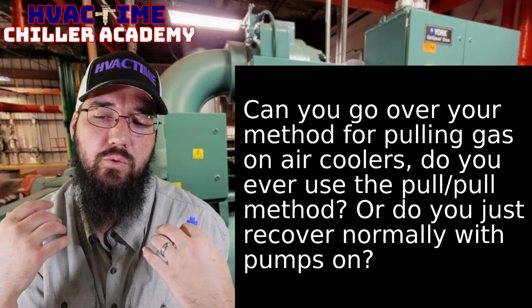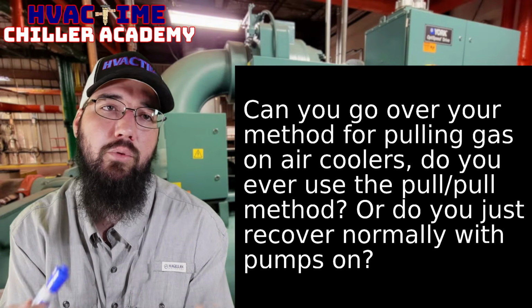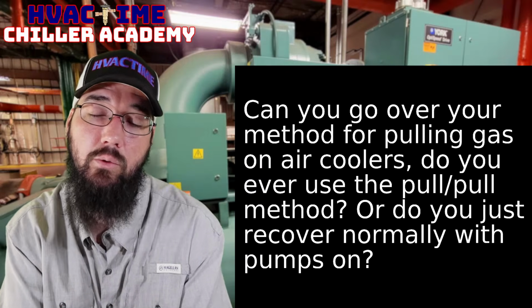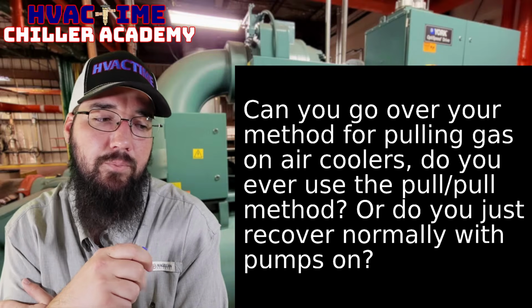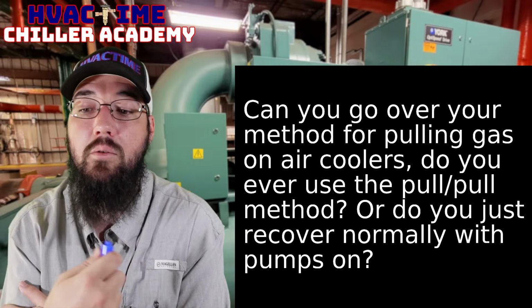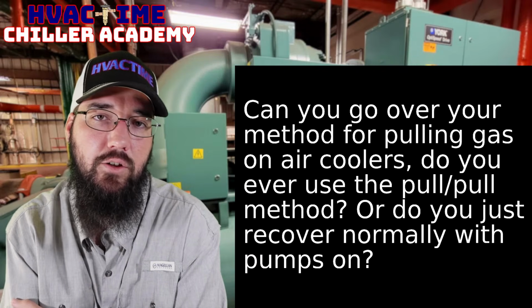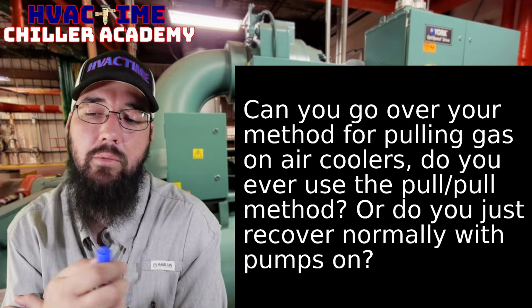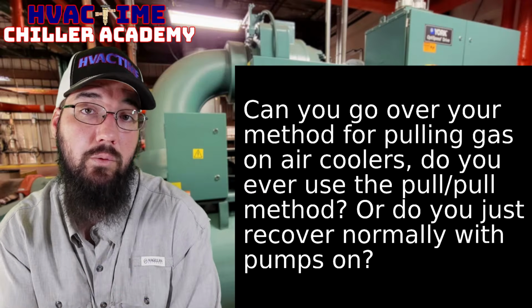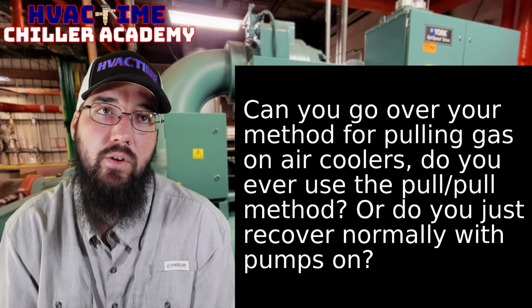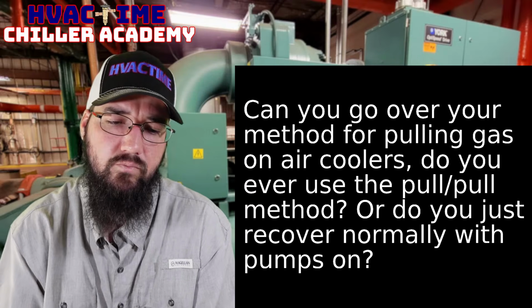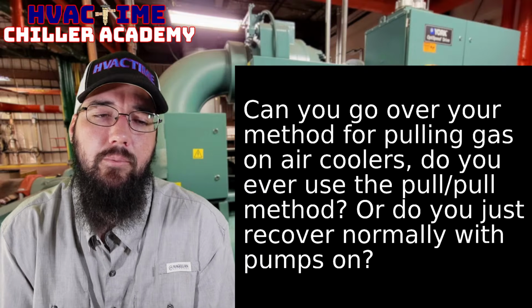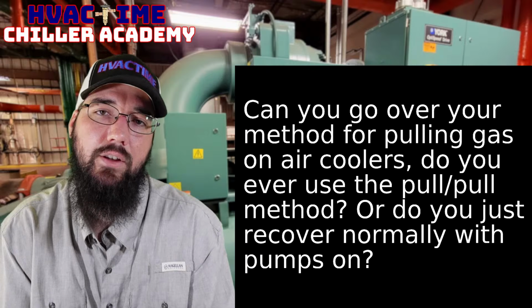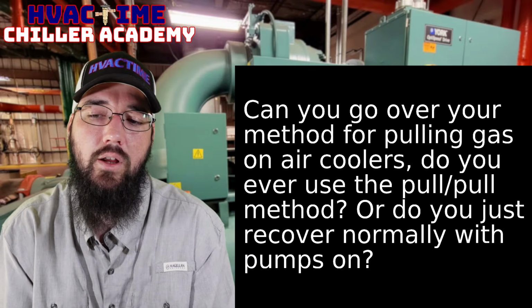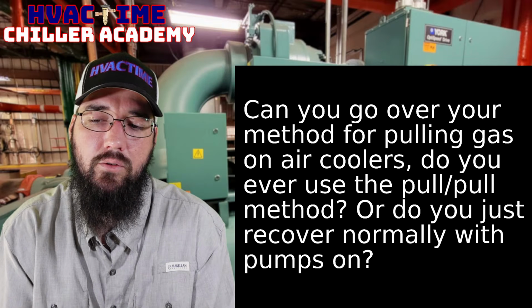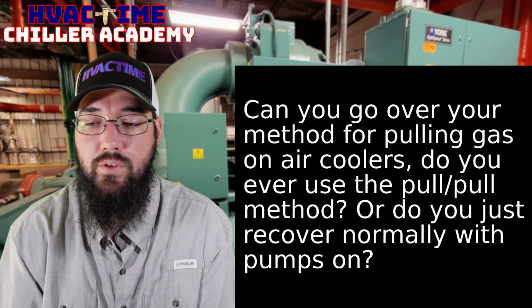As you step into larger tonnages and larger machines, we need to improve our practices to match the more advanced machines. So we have more advanced practices too. I'll throw using a cold trap in there as an example of a more advanced practice for evacuation and dehumidification that you're not going to learn about in school most of the time, and you're just not going to see on smaller equipment. But you will see it when we get into what we work on, especially since we work with hydronic evaporators and sometimes condensers if they're water cooled. So again, that's why it's a more advanced practice. It's taking it to a higher level.